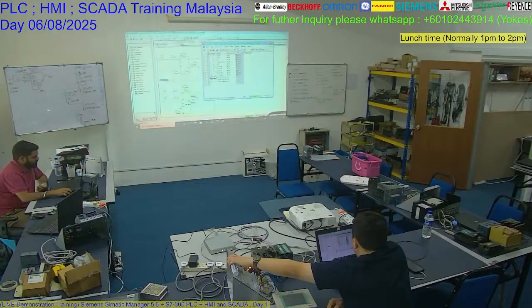License manager failed. Then I went to the Siemens website to see what the problem is. I found out they say version 6.0 has some security features. So when you do a Windows update, it updates your security and disturbs this file. In the Siemens system, they said to try version 6 service pack 12 and above, or 6.2. So I installed 6.2 and it can work.